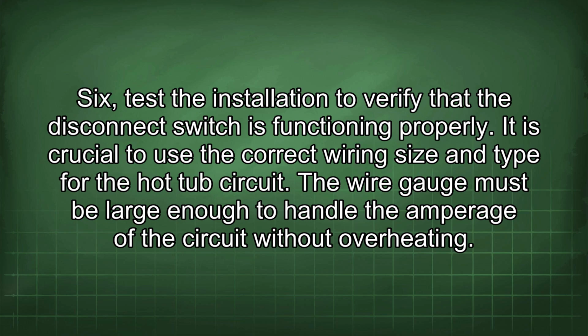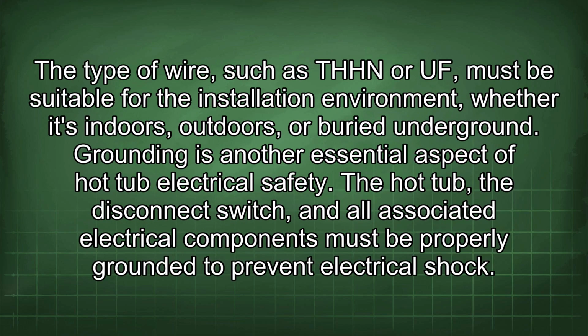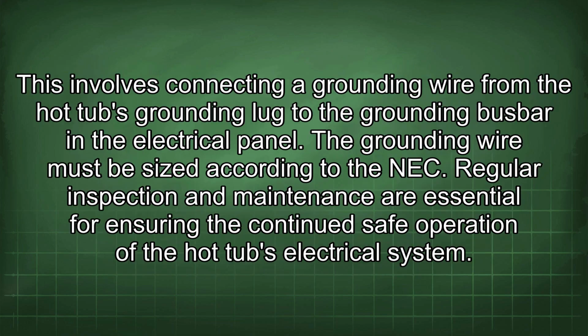It is crucial to use the correct wiring size and type for the hot tub circuit. The wire gauge must be large enough to handle the amperage of the circuit without overheating. The type of wire, such as THHN or UF, must be suitable for the installation environment, whether it's indoors, outdoors, or buried underground. Grounding is another essential aspect of hot tub electrical safety. The hot tub, the disconnect switch, and all associated electrical components must be properly grounded to prevent electrical shock. This involves connecting a grounding wire from the hot tub's grounding lug to the grounding busbar in the electrical panel. The grounding wire must be sized according to the NEC.